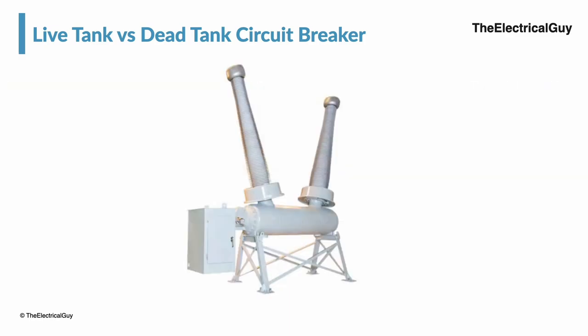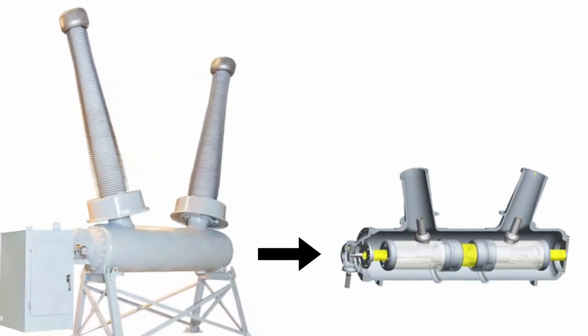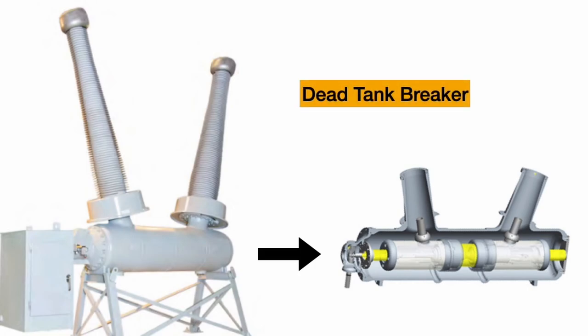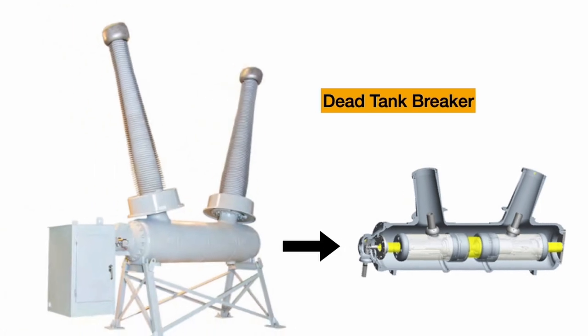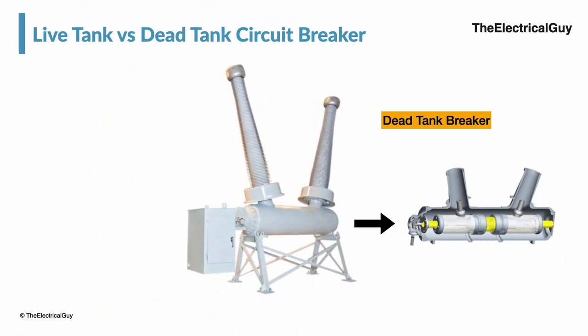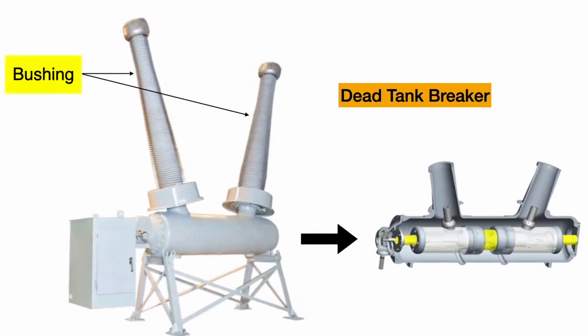Now focus on the circuit breaker shown — again, a single phase out of 3 phases. Here the interrupter is not in the top section. The interrupter of this circuit breaker is placed inside the bottom metal housing, which is completely grounded — it is at a dead potential. Hence such circuit breakers are called dead tank type circuit breakers. The tank is completely filled with a dielectric medium like SF6 gas, which insulates the live contacts from the metal tank. To connect the incoming and outgoing supply, outdoor bushings are used.